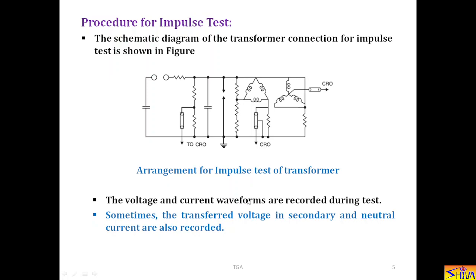The voltage and current waveforms are recorded during test. So, it is necessary to record the voltage as well as current waveform. Sometimes the transferred voltage in secondary and neutral current are also recorded. So, when we want to record the neutral current and the secondary current or secondary voltage, we have to use DSO. Here I have shown the neutral point recording of the neutral current.